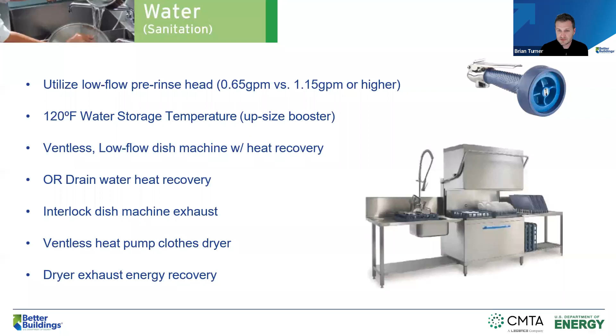One other strategy that we've seen, if you can maintain your water temperature at 120 degrees instead of 140 degrees from your water heater, you can save energy in that way, but you will need to upsize the booster heater in these dish machines because they generally are going to need 180 degrees. Again, there are huge discrepancies in the flow rates for pre-rinse heads. Typically you're going to use a pre-rinse function for dishware before you put it in the dish machine, and that can have a big effect on the amount of hot water that's being used for these processes.